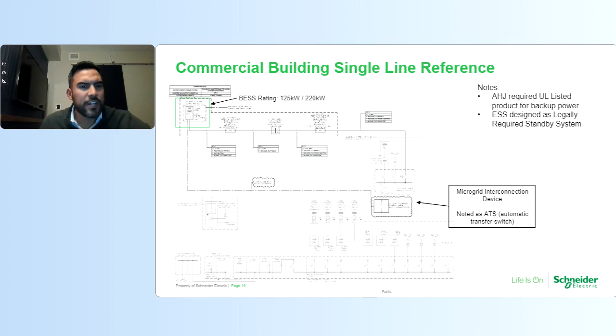And this was a small energy storage system, about 125 kW rating. But I'll say for most commercial applications, again, it goes to that sweet spot, primarily 100 to 500 kW. You'll have some times where they go up to 1 megawatt, have multiple 1 megawatt energy storage systems. Really anything over 1 megawatt, those are used primarily for grid connected use cases. You can also use them for resiliency. It's just at that time you're dealing with a lot more power. So the use cases change, but conceptually, they all have the same functionality. They can operate in resiliency as well.